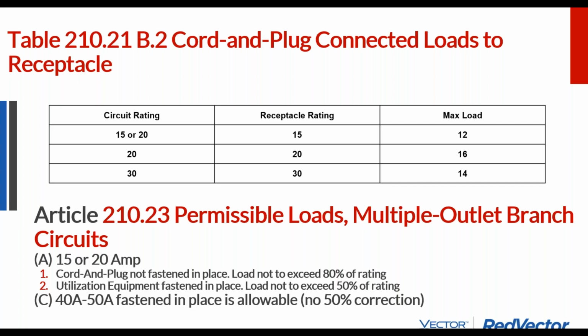If you put 20 amps of load on a 20 amp breaker, you'd be tripping your breaker all the time, because it would run up to that 20 amps and then heat up the wire to where it should be at 20 amps and then pull open the breaker. That does in fact mean that you can run at a higher amperage than what the breaker is rated for a brief period of time before it trips, such as a surge load that might only last for a minute.